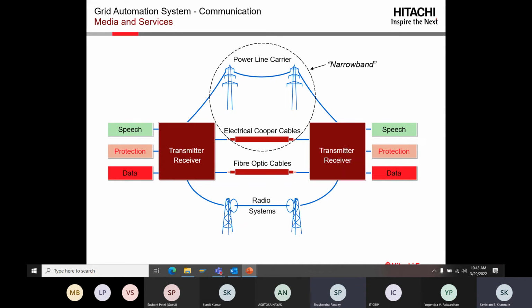If it is point to point, single user. Pandey here: when we say narrowband, basically we talk of 4 kilohertz bandwidth per channel. That 4 kilohertz bandwidth is divided to be used for speech, data, and teleprotection also. Being narrow, in one terminal you can handle one or two, maximum three channels per transceiver. Overall, the band available for power line is from 50 to 500 kilohertz in India.